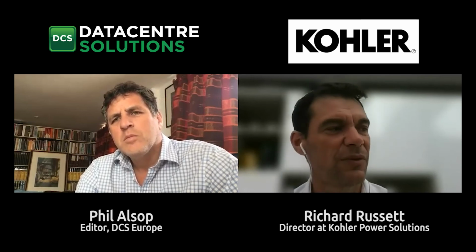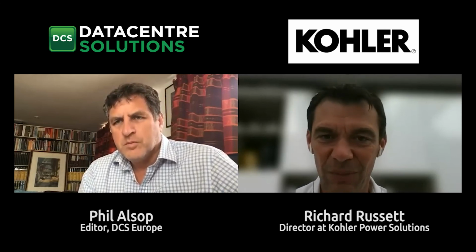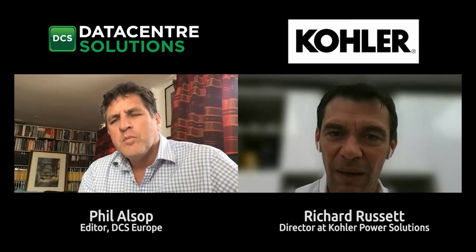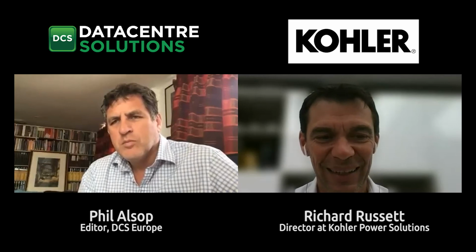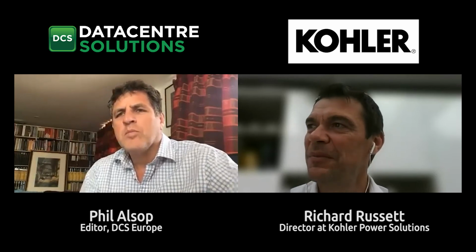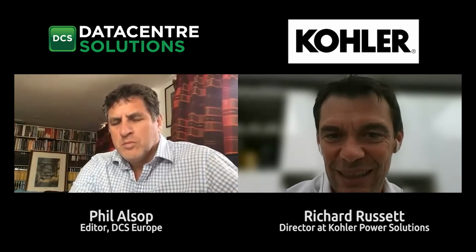In terms of other technologies, yes, there are issues with certain technologies. Diesel engines are very good when you start the machine. You start the machine and seconds later you've got power available and you can run the site. It's not quite as rapid for some other technologies in terms of time between an outage and the ability to provide full power. So it's the diesel technology we apply today. It ticks a lot of boxes in terms of what customers are looking for. And again, we see sites where even when they're looking at gas gensets, for example, there's still diesels involved, because the ability of a gas engine to run up quickly and support a large load is not as good as a diesel engine, similar to your car.